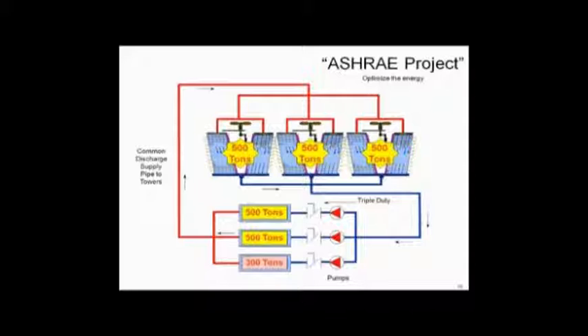So we can just get by on the chiller. To keep it simple, I'm going to use a 10-degree range, which means my pumps would be 1,500 GPM, three GPM per ton on my 500-ton chiller, and of course, three GPM per ton on the 300-ton chiller. So how are you going to run that little small 300-ton chiller in the wintertime? How are you going to stage it?